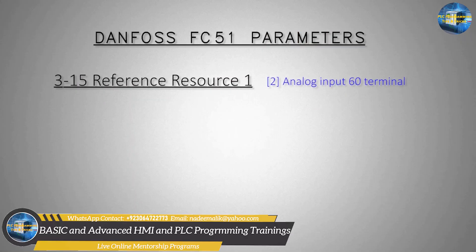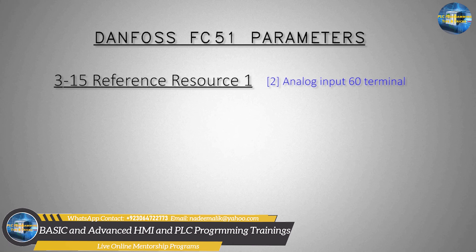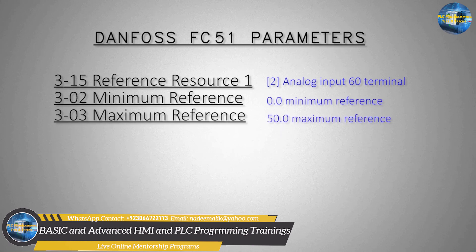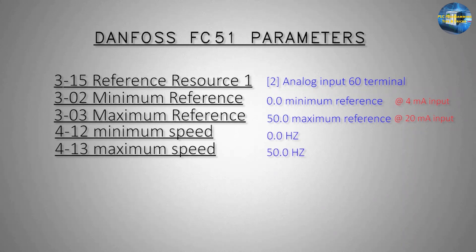Next we have to set some parameters in the FC51 inverter to be able to send and receive analog signals. First we set parameter 3-15 to 2, which configures terminal 60 of the VFD as analog input speed reference. Next we set parameter 3-02 minimum reference as 0.0 and parameter 3-03 maximum speed reference as 50.0. At 4 milliamps the VFD runs at 0.0 Hz, and at 20 milliamps at terminal 60 the motor runs at 50 Hz.